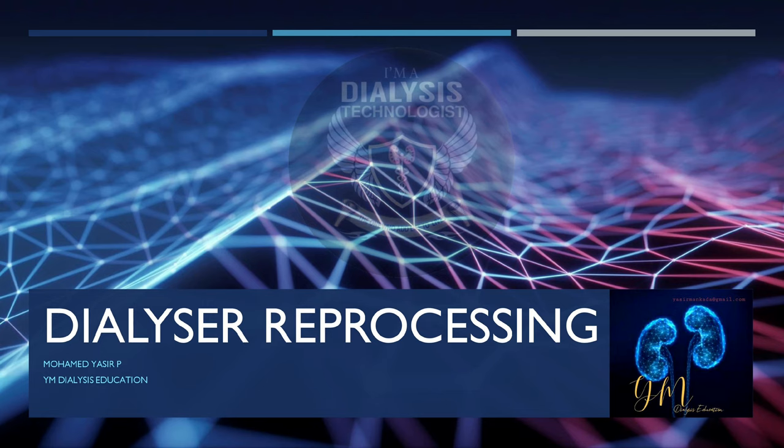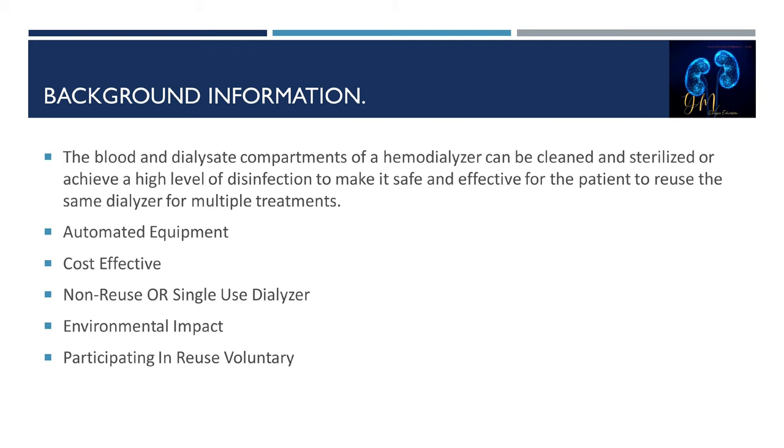Today we are going to discuss about dialyzer reprocessing. The blood and dialysate compartment of a hemodialyzer can be cleansed and sterilized or achieve a high level of disinfection to make it safe and effective for the patient to reuse the same dialyzer for multiple treatments. Reprocessing is a common practice in many dialysis units. Originally reprocessing was done by hand, but now it is most often done with automatic equipment.